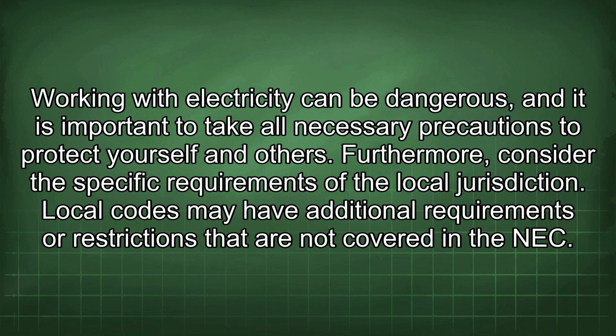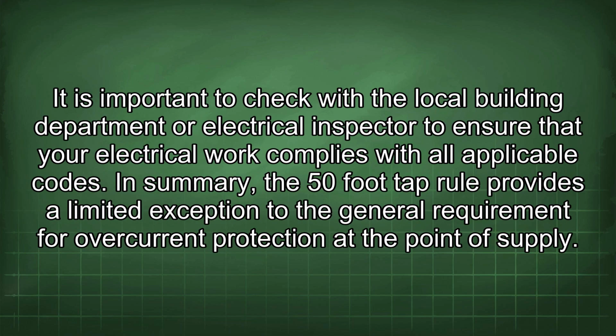Furthermore, consider the specific requirements of the local jurisdiction. Local codes may have additional requirements or restrictions that are not covered in the NEC. It is important to check with the local building department or electrical inspector to ensure that your electrical work complies with all applicable codes. In summary, the 50-foot tap rule provides a limited exception to the general requirement for overcurrent protection at the point of supply.